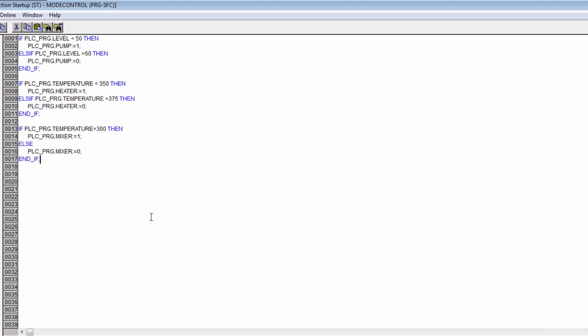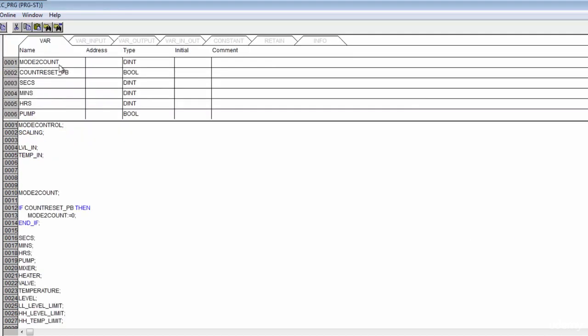And there's one more thing that I wanted to think about here, and that is that we actually want all of these devices to actuate on a timer. So we want these to come on a delay, and we want those to go off on a delay. So we actually need some delay logic, because right now we're just hard starting all of these things. We're turning them on immediately, turning them off immediately. So we need to have a 5-second delay, which means we're going to have a little bit more logic.